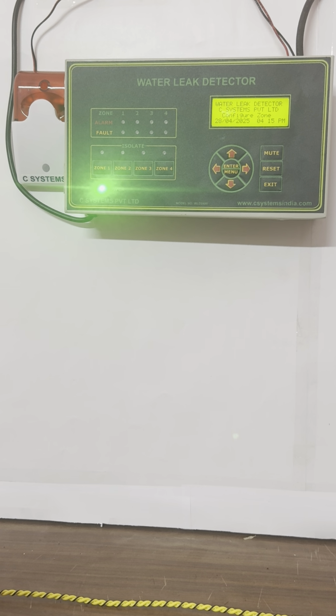So in this video, I am going to explain the installation procedure, followed by a live demo of the 4-zone water leak detection system with the functionality and features that are embedded in the panel itself. The 4-zone water leak detection system is a wall mountable panel. It can ideally be fixed at about 5 feet above the ground, ensuring easy access for monitoring. Connect the power supply to a 230 volt UPS power socket. The panel comes along with a 2-meter power cord.